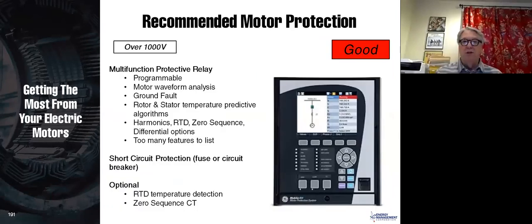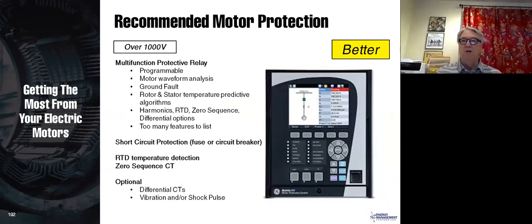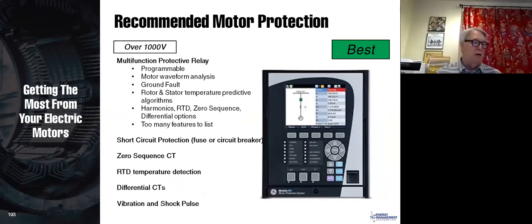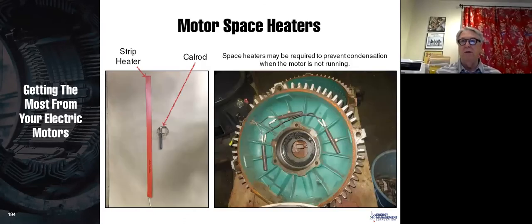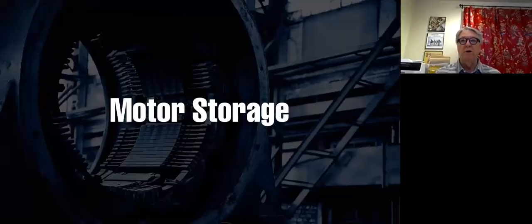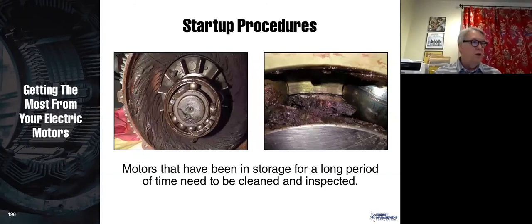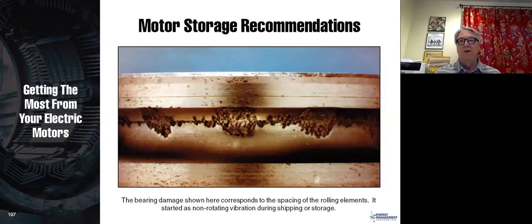There's differential protection, and over 1,000 volts, there's your good protection, your better protection, and your best protection. And we've recommended all the things that you should have to protect your motor, and that will be in your slide pool. Motor space heaters are good when you think that there might be condensation within the motor. Then motor storage: anytime you put it into motor storage, you must go through procedures for that. And guess where you can find those procedures?